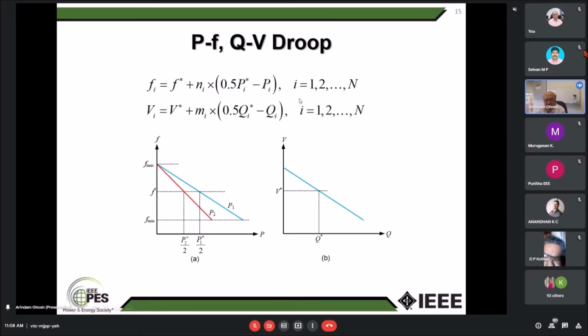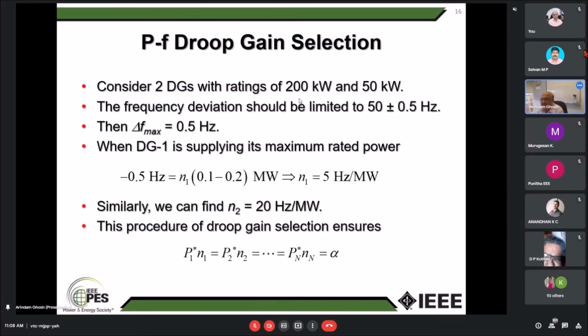So anyway, let's look at a simple calculation. Suppose you have two DGs with ratings of 200 kilowatt and 50 kilowatt. So you can see DG1 is rated 200 kilowatt, DG2 is rated 50 kilowatt. So this is 4 times the size of this one. That means if I have, say, a load, and I divide that load by 5, then this one will supply 4/5 of that load, and this one will supply 1/5 of the load. Suppose the total load is 250 kilowatt, then this supplies 200 kilowatt, this supplies 50 kilowatt. If the load is just half of it, 125 kilowatt, then it should supply 100 kilowatt, this should supply 25 kilowatt, so that their proportion is 4:1.